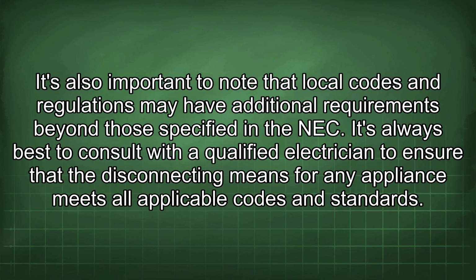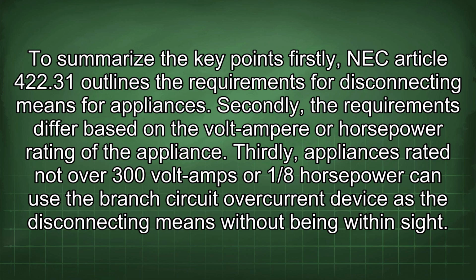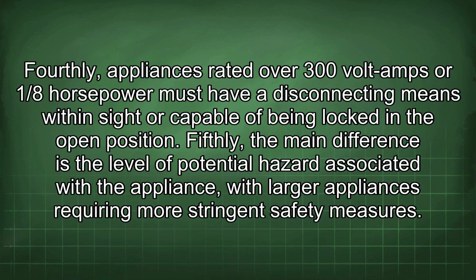To summarize the key points, firstly, NEC Article 422.31 outlines the requirements for disconnecting means for appliances. Secondly, the requirements differ based on the volt-ampere or horsepower rating of the appliance. Thirdly, appliances rated not over 300 volt-amps or 1/8 horsepower can use the branch circuit overcurrent device as a disconnecting means without being within sight. Fourthly, appliances rated over 300 volt-amps or 1/8 horsepower must have a disconnecting means within sight or capable of being locked in the open position. Fifthly, the main difference is the level of potential hazard associated with the appliance, with larger appliances requiring more stringent safety measures.